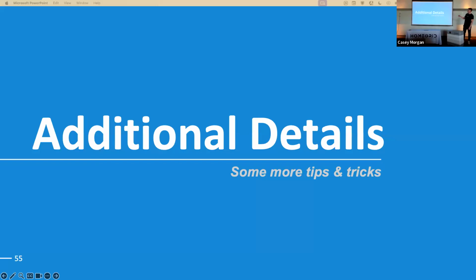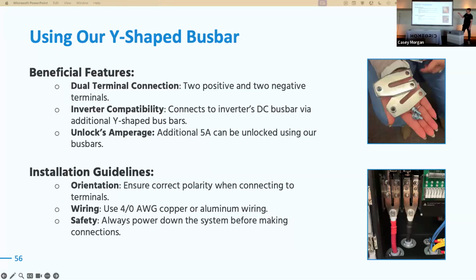Additional detail: if you're using the SolArk 15K, it has 2 negative and 2 positive landings for the battery cables. Without bus bars, you'd have to choose just one negative and one positive. The problem is that doing that with SolArk limits the output to about half its capability to charge and discharge the battery. It's a weird little niche issue.